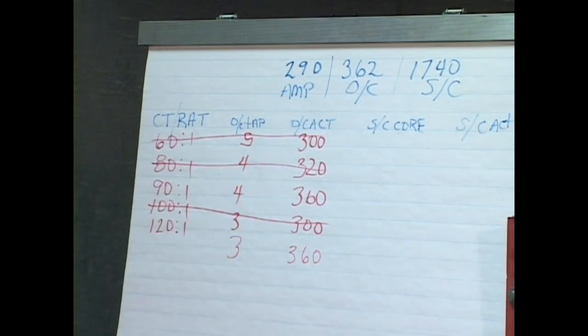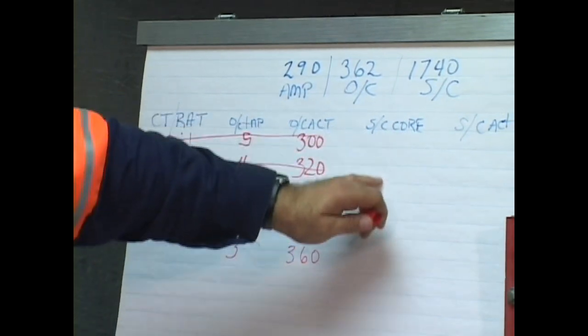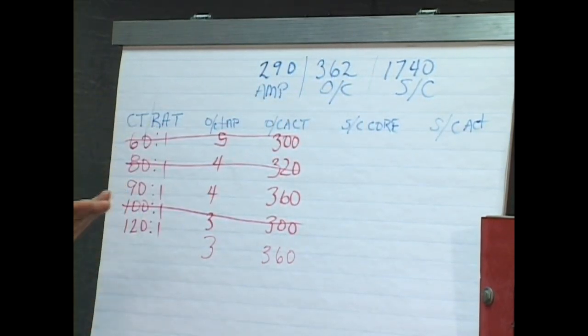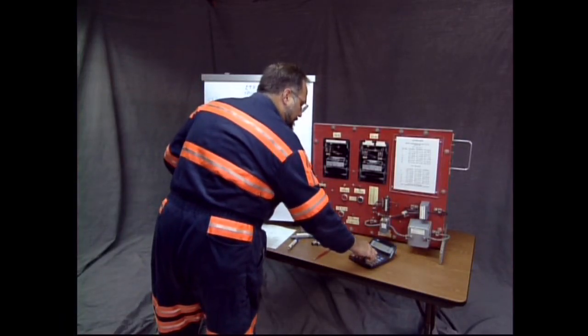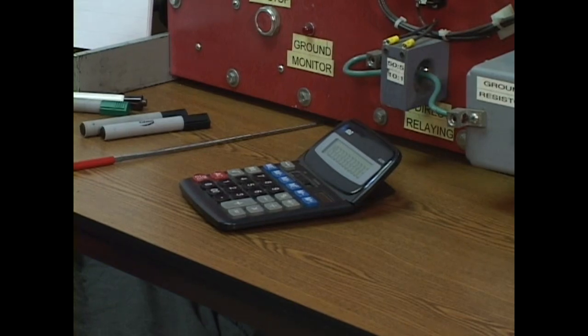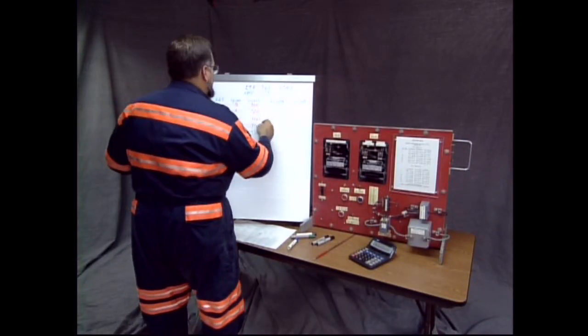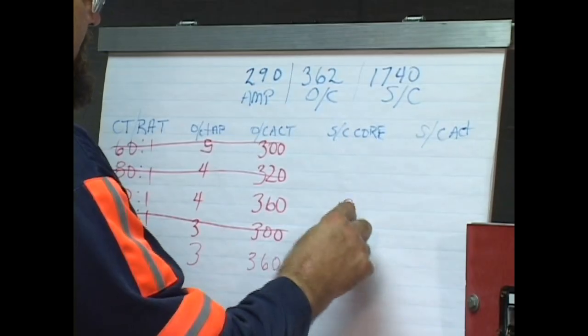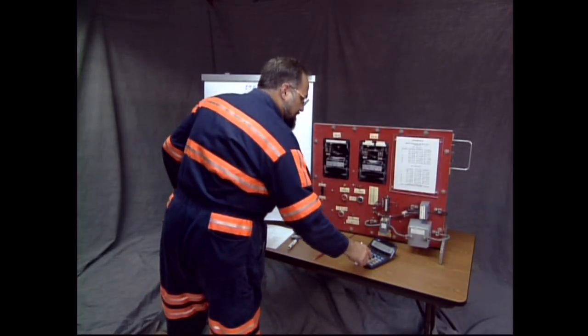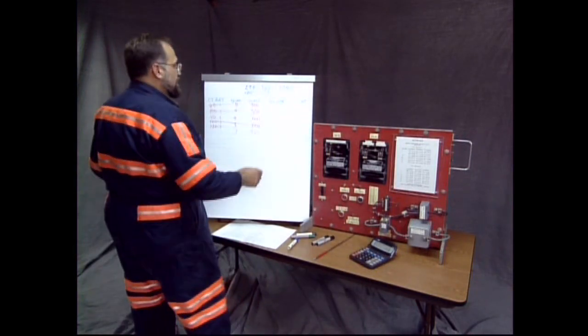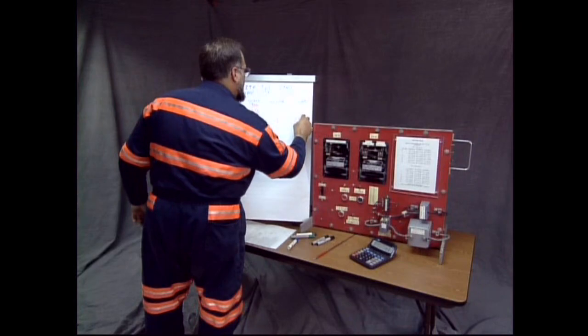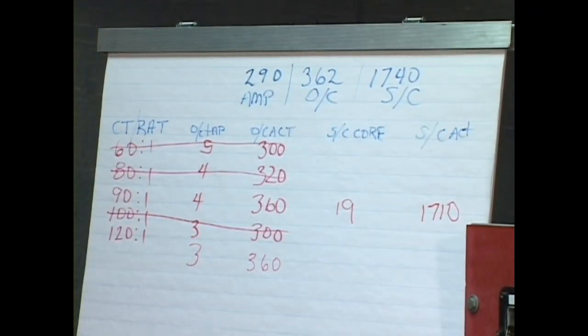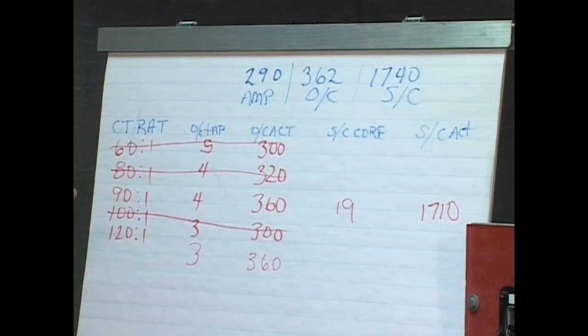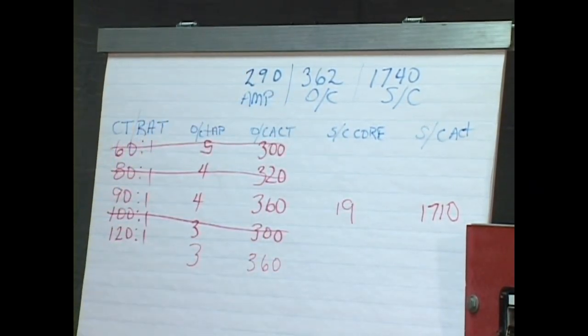So using that, we're now going to use the short circuit maximum setting to find the core. We use the 1740 in place of the 362, and divide that ratio into 1740. Let's take 1740 divided by 90. That equals 19.333. So let's just round it down to the nearest whole number, for a core of 19. Now, 19 times 90 is 1710. If I chose a core of 19 and a CT of 90, my relay would act upon 1710 amps.